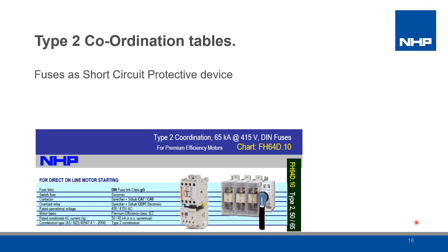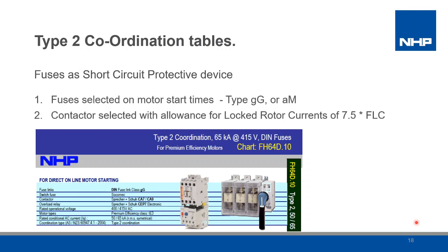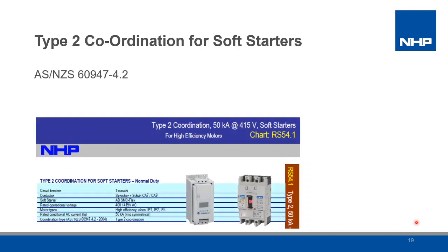Fuses as a short circuit protective device are now less utilised as MCCB technology in energy limitation has increased. Fuses can still offer a more compact solution, especially at 690 volts, as the fuses are I2T based, plus the instantaneous inrush of premium efficiency motors does not cause the same issues. Type 2 coordination for soft starters also exists.